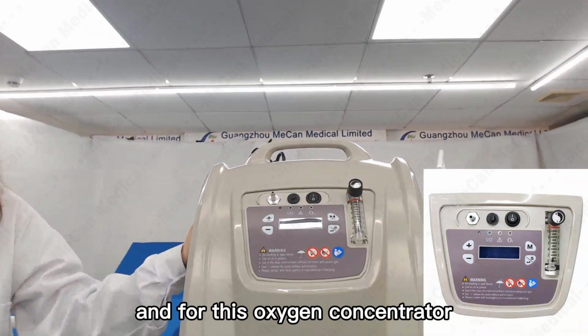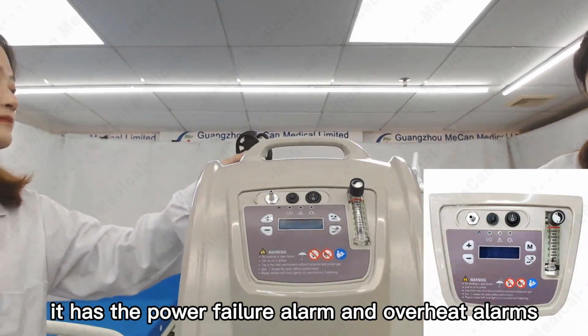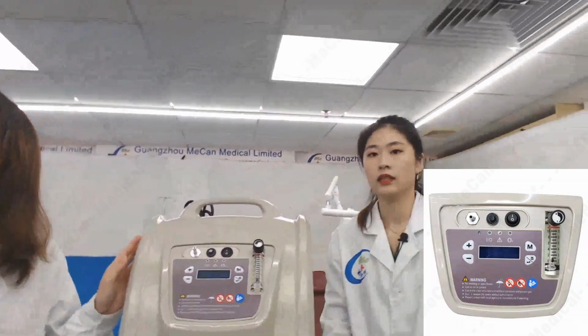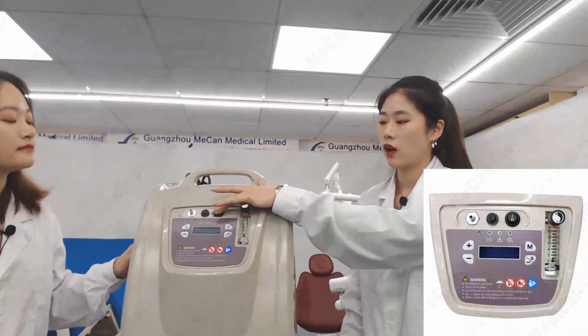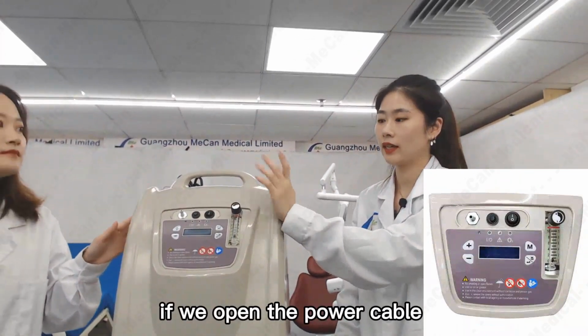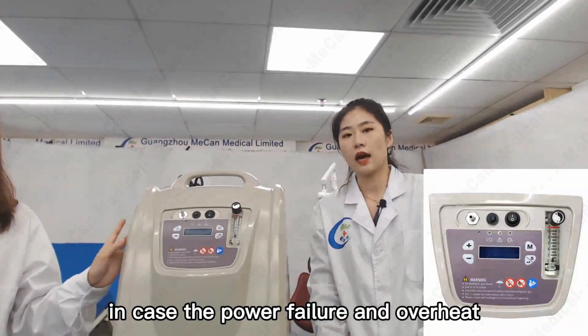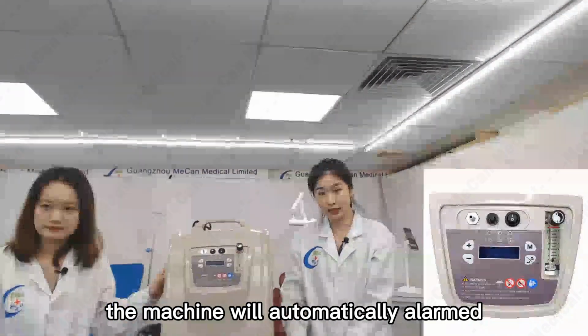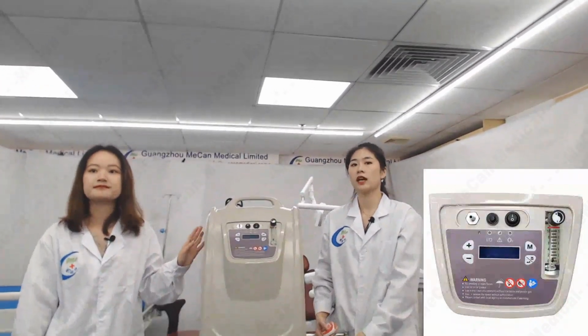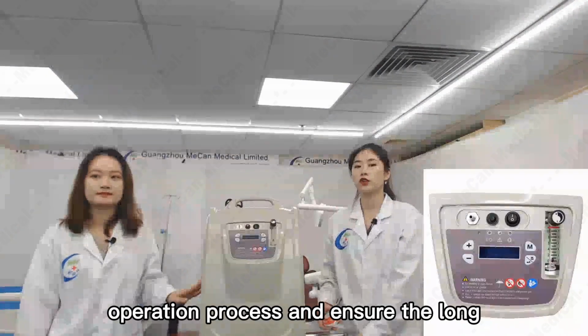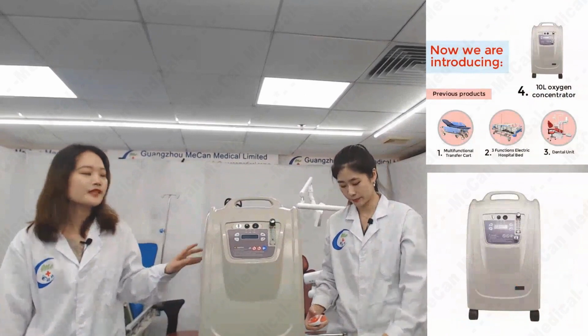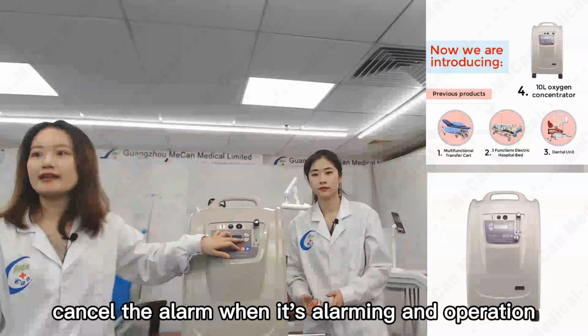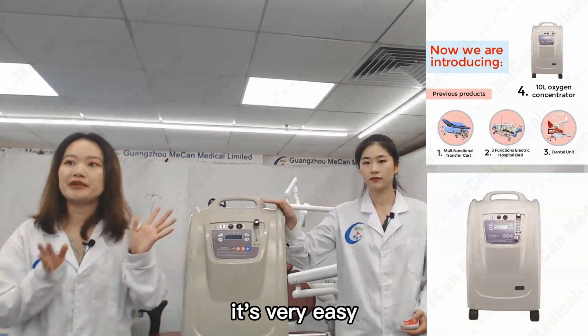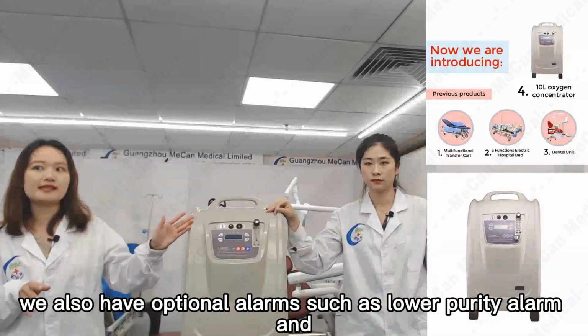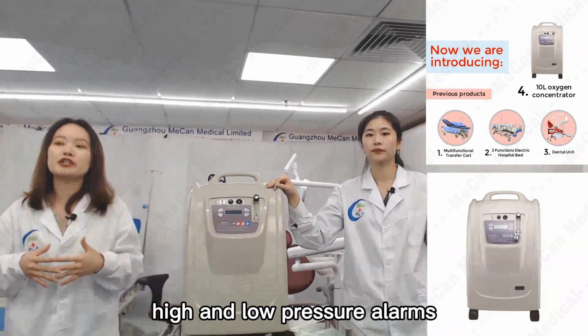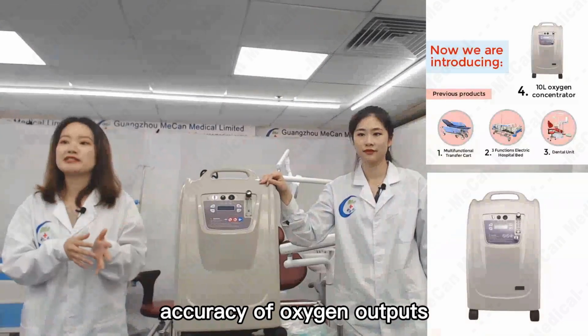This oxygen concentrator has a power failure alarm and an overheat alarm. Like this: when it's not connected to the power, if we open the power cable, just like this. In case of power failure or overheating, the machine will automatically alarm to remind users to check the machine in time. These 2 alarms ensure the safety of the operation process and ensure the long service life of the machine. You can press this button to cancel the alarm when it's alarming, and the operation is very easy. In addition, we also have optional alarms such as lower purity alarm and high and low pressure alarms. These additional alarms can ensure the accuracy of oxygen output.